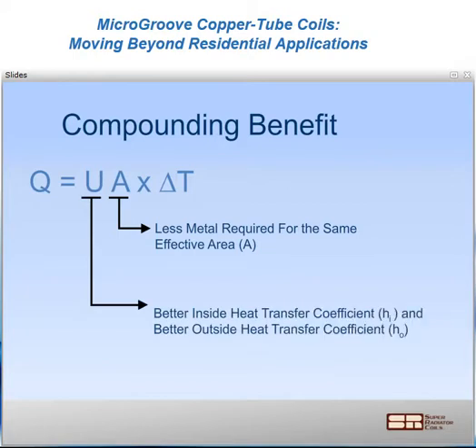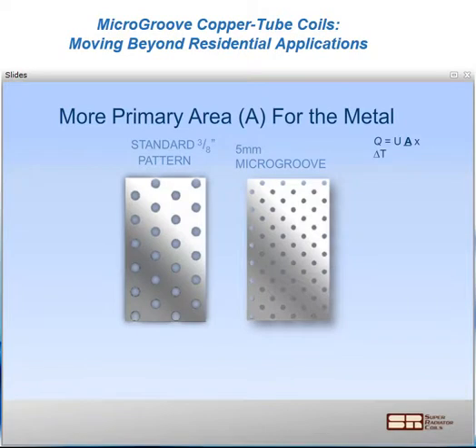But more exciting is that we were able to validate in the lab that we see better inside and external heat transfer coefficients, so we get this multiplicative effect. Let's take a closer look. Here I have the basis of comparison using a traditional 3/8 copper tube coil next to its 5mm MicroGroove counterpart. Think of this as a cross-sectional area driving our primary heat transfer surface. If we sum up the circumference of each of those primary surface areas, in the 5mm tube we have 40 inches, or 40% more, in the sum of the circumference or primary surface.